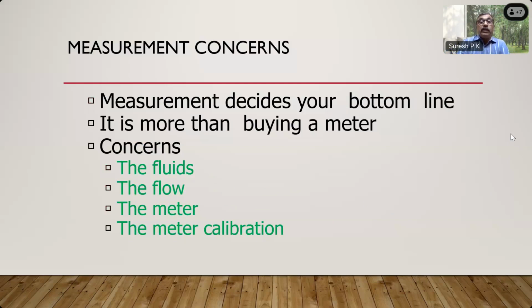So the measurement decides your bottom line, as you know. It is more than buying a meter. The fluid flow measurement is affected by the fluids. It is affected by the flow. It is affected by the meter. It is affected by the meter calibration also. The fluids, what are the kinds of fluids which are being measured? What are the types of fluid impurities which are associated with the fluid? What are the phases of the fluid?